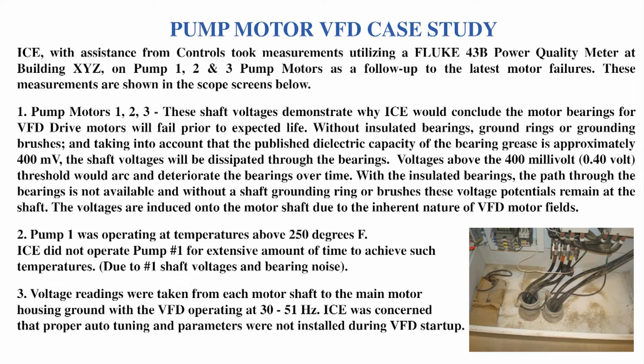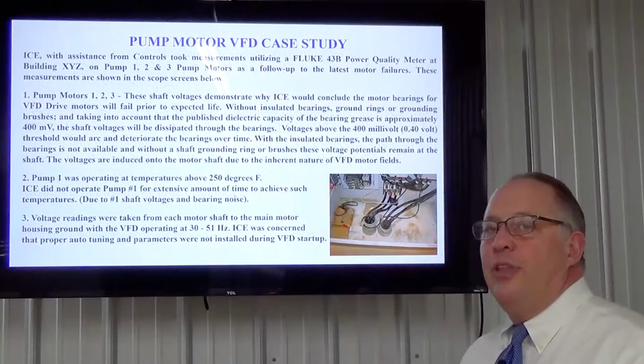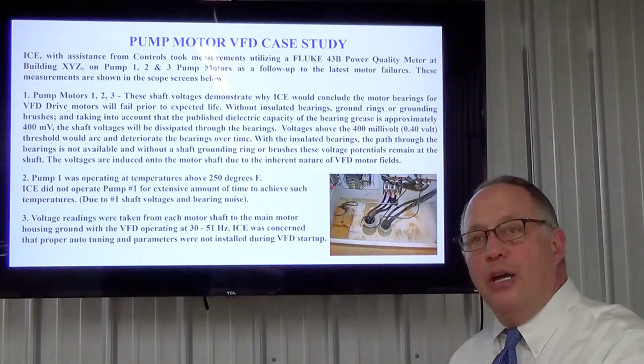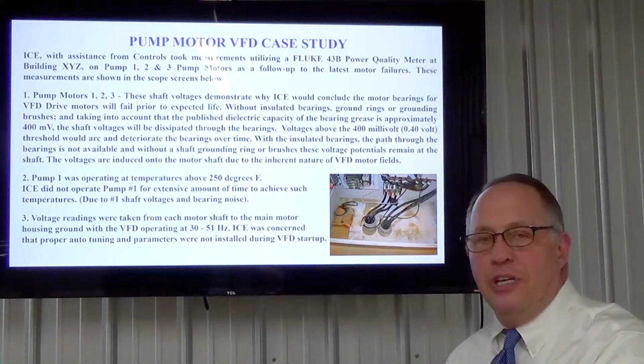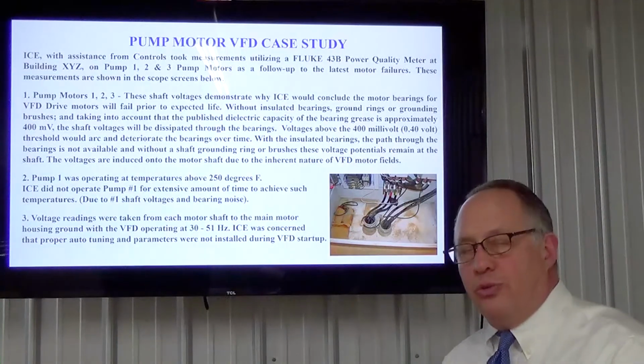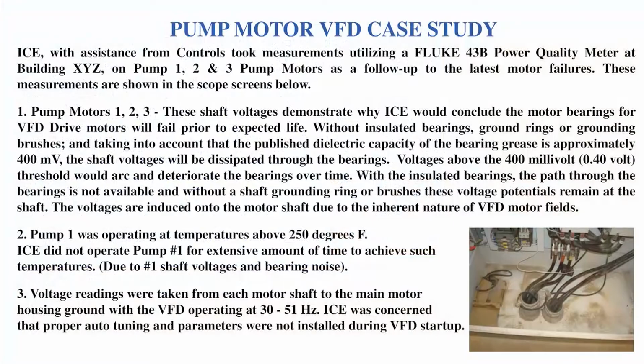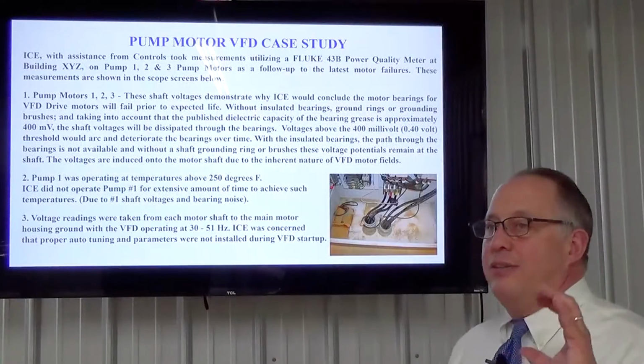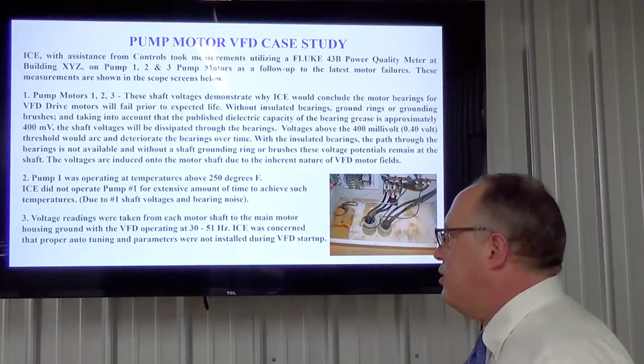Number 2, pump 1 was operating at temperatures above 250 degrees Fahrenheit. That was measuring the outside of the motor housing itself. Extremely warm, and when we checked into it, it was starting to make some noise. We did not operate pump 1 for an extensive amount of time to achieve those temperatures, due to, number 1, shaft voltages and bearing noise. So we just ran that long enough to get the readings.